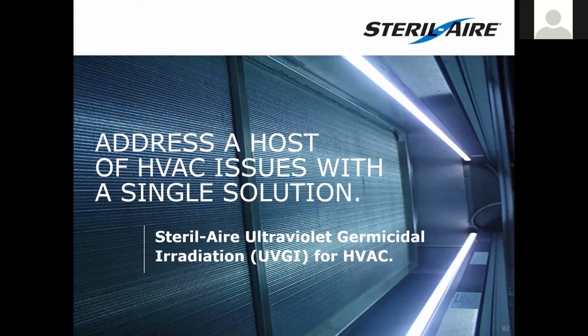One last question. How did you measure the irradiation? How did you measure the one on the coil? Did you use a thermograph to check on the coil? What tool did you use? I use a certified radiometer. A radiometer. So that gives me my output on the coil if I'm commissioning.